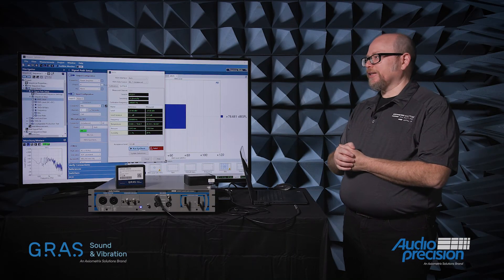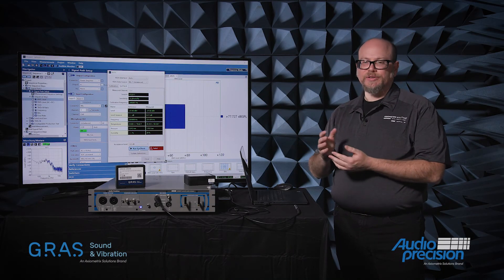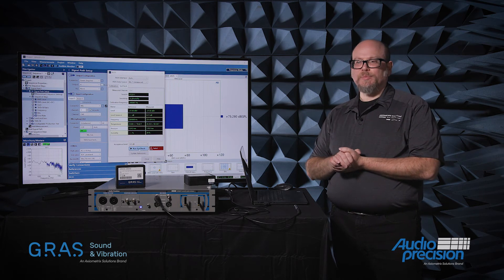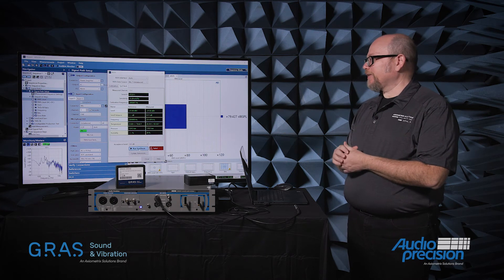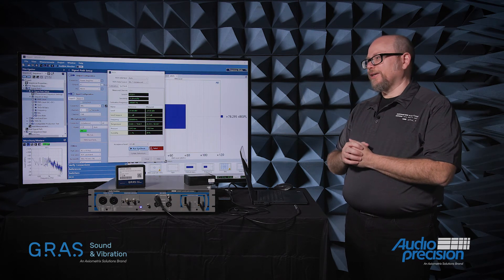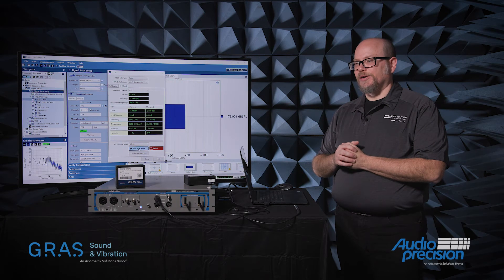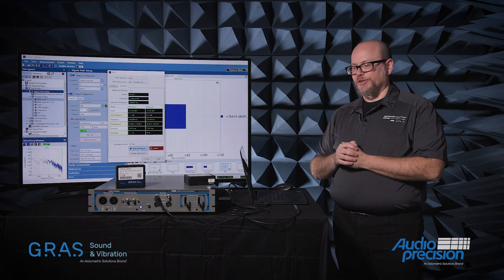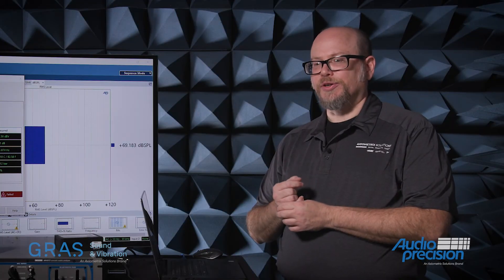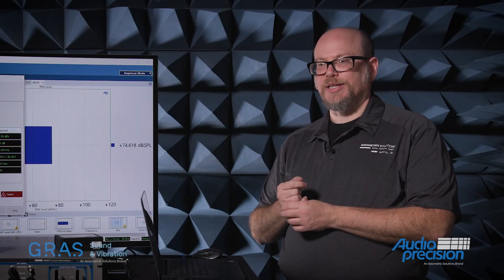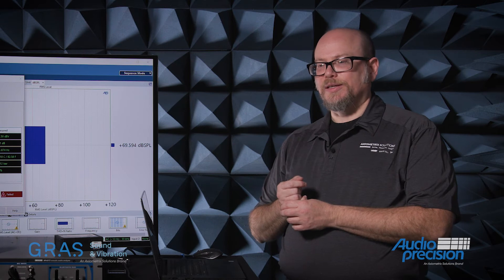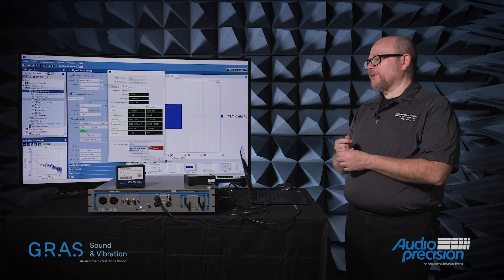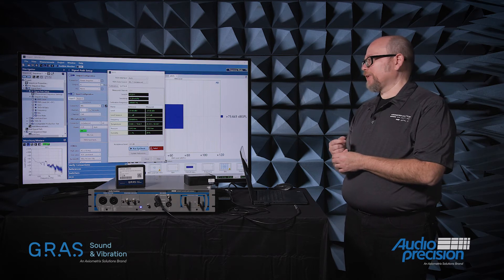In this case, I decided that my acceptance level — or actually the default acceptance level — would be 0.3 dB. Now it has failed. What the system has done is measured the value of the reference signal generator, compensated for the ambient temperature. There are actually temperature, humidity, and static pressure sensors embedded in this microphone as well, and algorithmically determined that we are not within 0.3 dB accuracy.